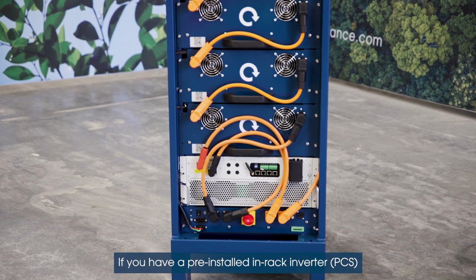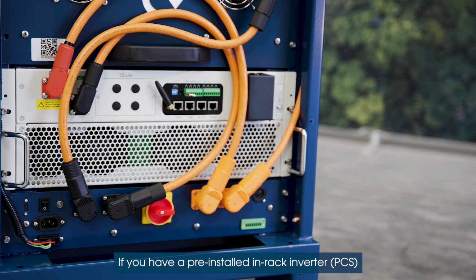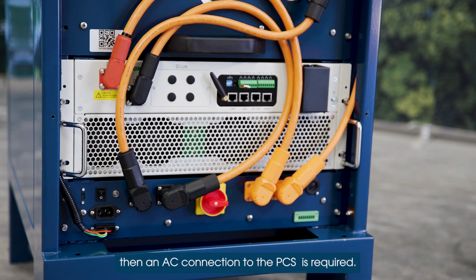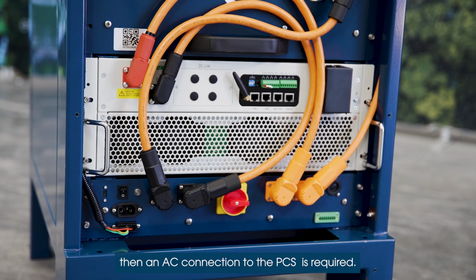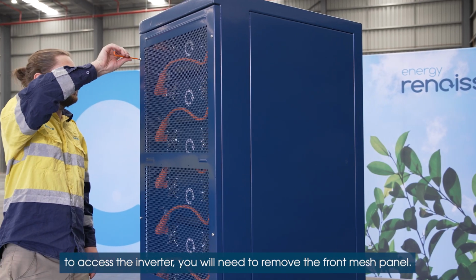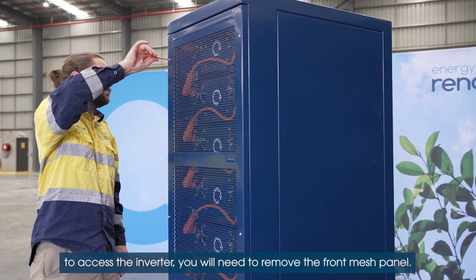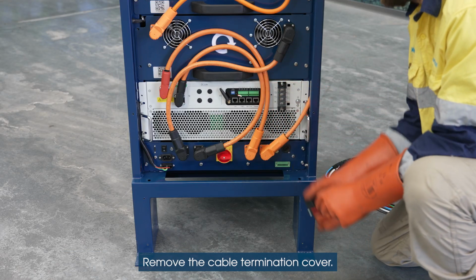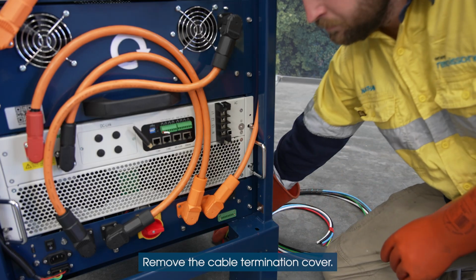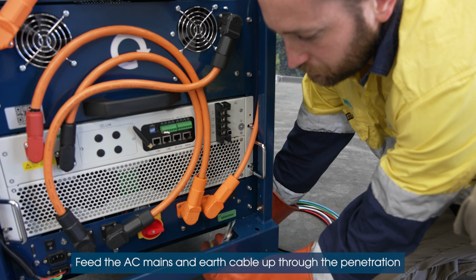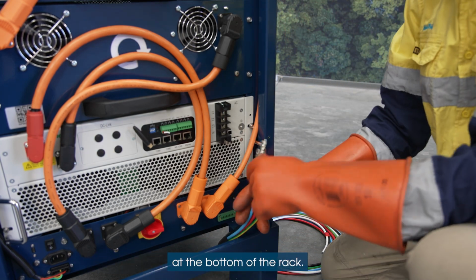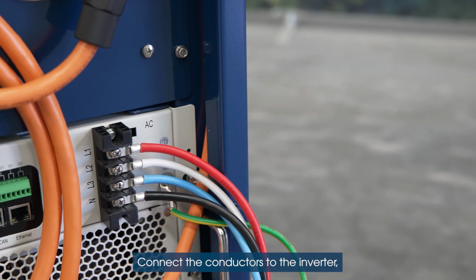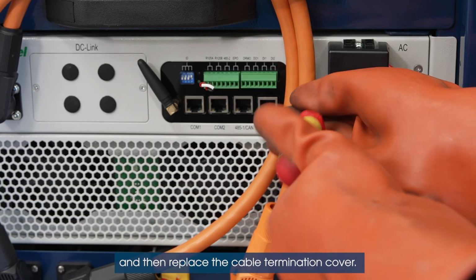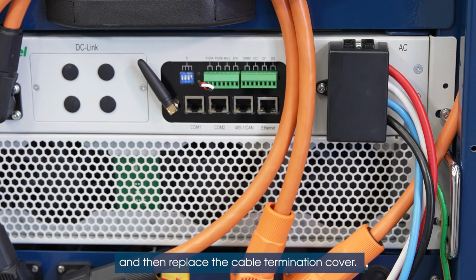If you have a pre-installed in-rack inverter, PCS, then an AC connection to the PCS is required. To access the inverter, you will need to remove the front mesh panel. Remove the cable termination cover. Feed the AC mains and earth cable up through the penetration at the bottom of the rack. Connect the conductors to the inverter and then replace the cable termination cover.